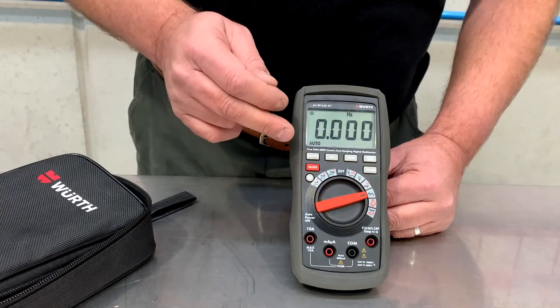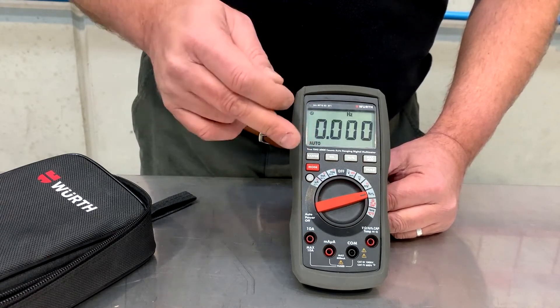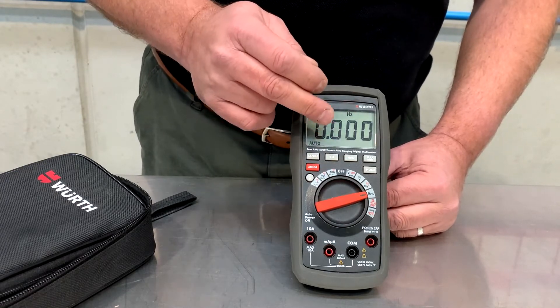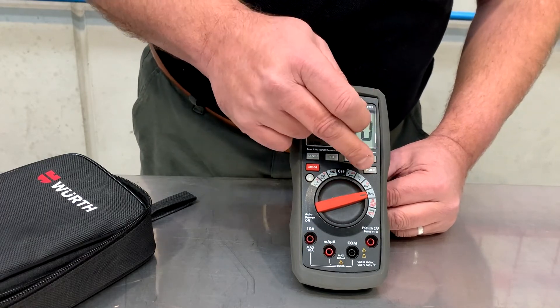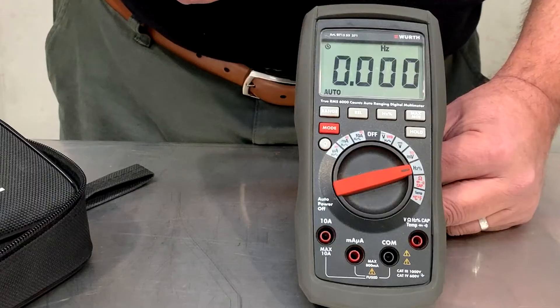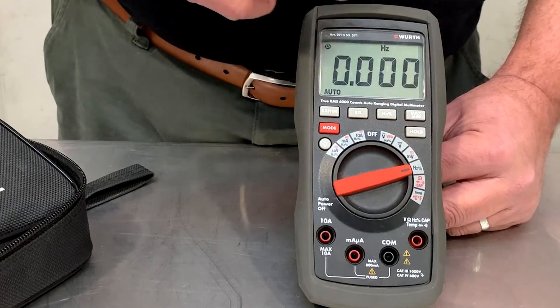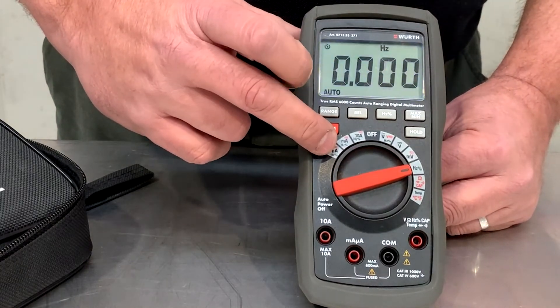Just above the dial on the multimeter we have some function buttons. The range button turns off the auto ranging. Then we have the relative button, which holds a stored value so you can compare it against another. We have a min/max button. Then we also have a hold button which freezes your reading on the screen. We also have a mode button which cancels the auto turn-off function. If you don't push this button, the multimeter will automatically turn off after 90 seconds.